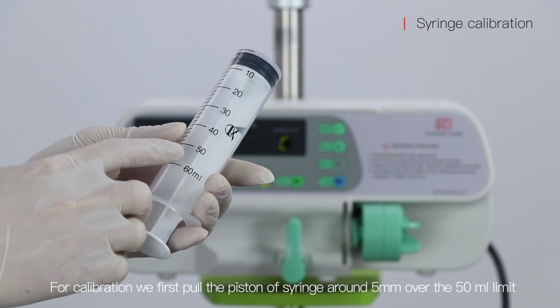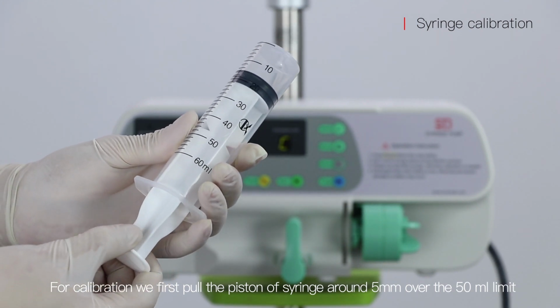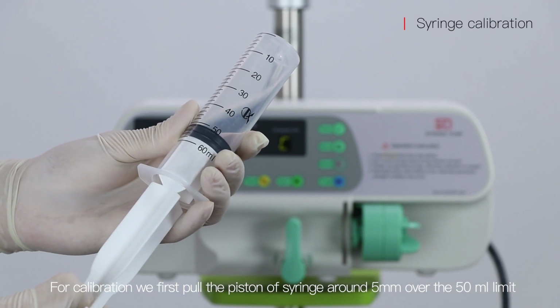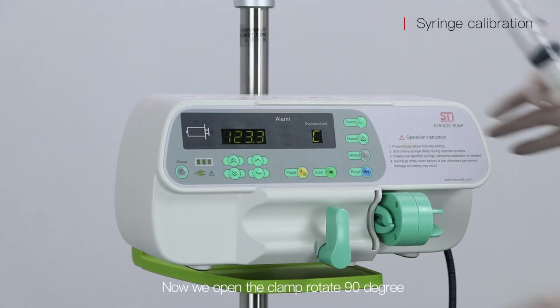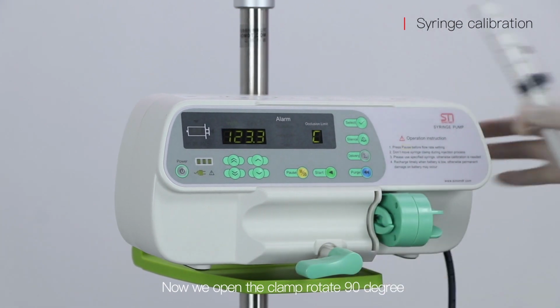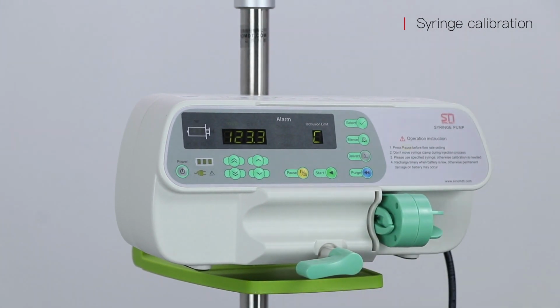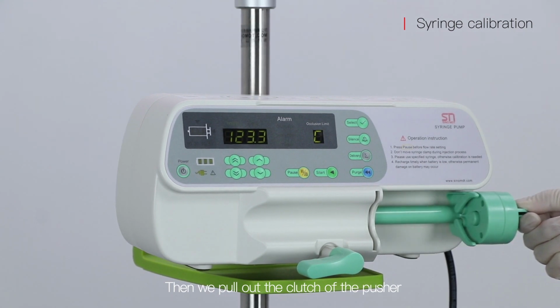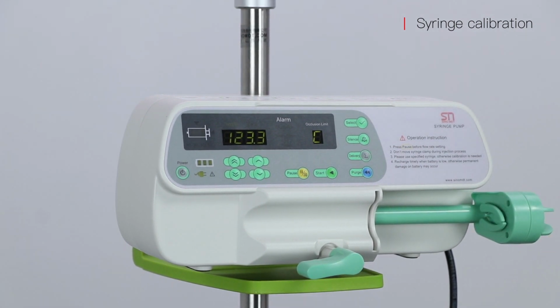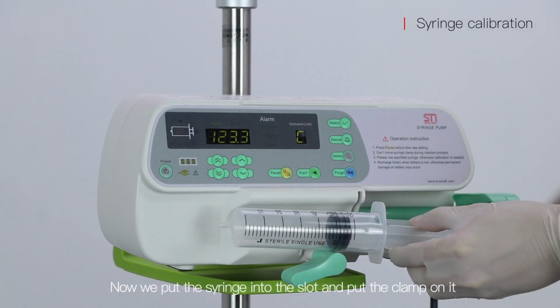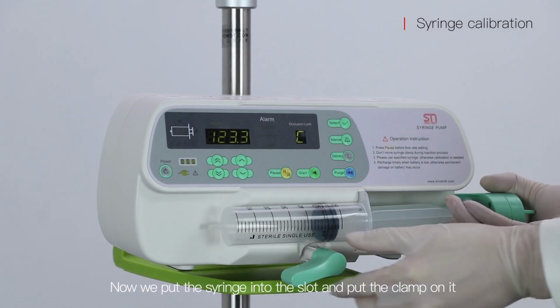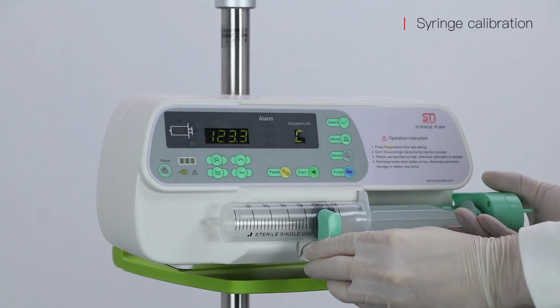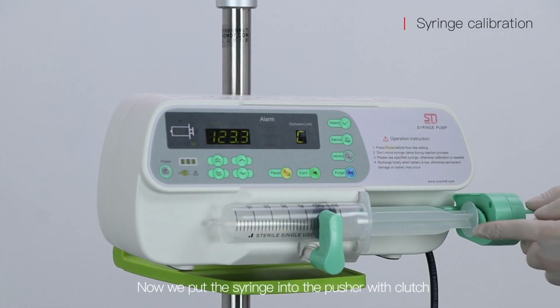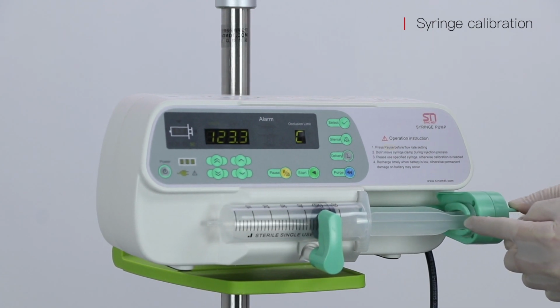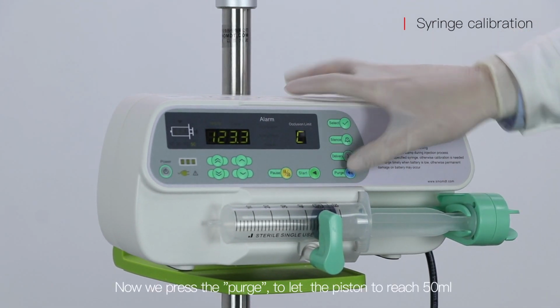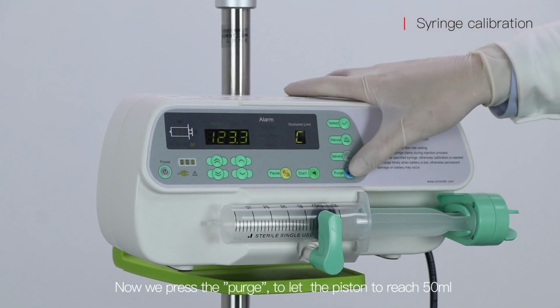For calibration, we first pull the piston of the syringe around 5 mm over the 50 ml limit. Now we open the clamp, rotate 90 degrees. Then we pull out the clutch of the pusher. Now we put the syringe into the slot and put the clamp on it. Now we put the syringe into the pusher with the clutch. Now press the purge to let the syringe reach the 50 ml.